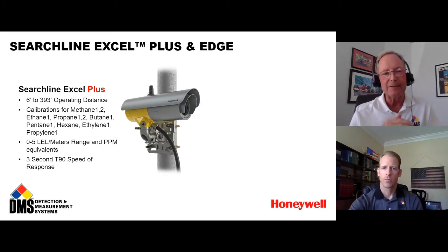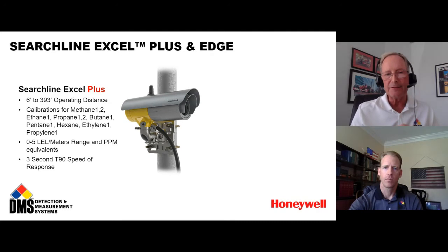The range of detection is 0 to 5 LEL meters. Now, this is a volumetric range, not a concentration, 0 to 5 LEL meters. That can also be provided to you as a ppm equivalent. So that's something new with the Searchline Excel Plus and the Edge, is that we can share this information as ppm measurements rather than percent LEL meter measurements. And then this is an immensely fast responding detector with a T90 response of 3 seconds. So very, very rapid detection. So for applications where you are looking at areas, distances, let's say just under 400 feet, the Searchline Excel Plus is what you would go with.